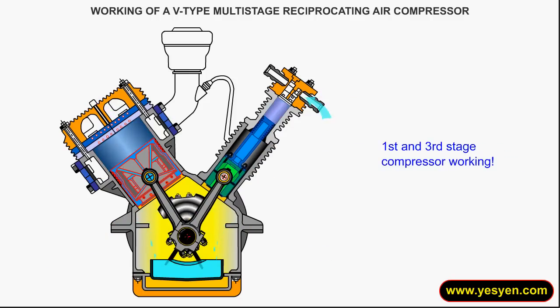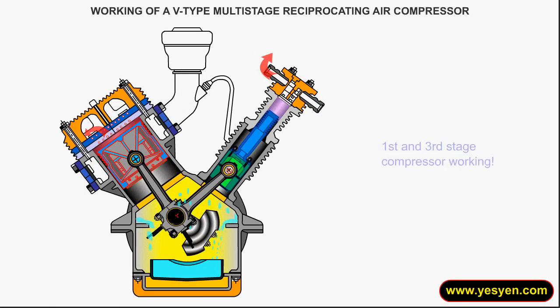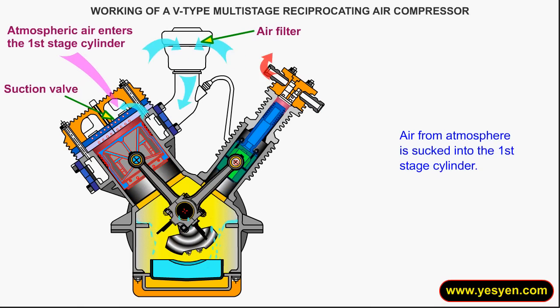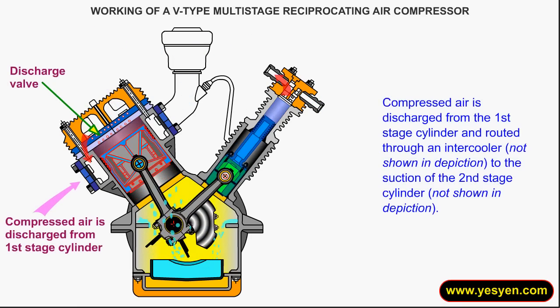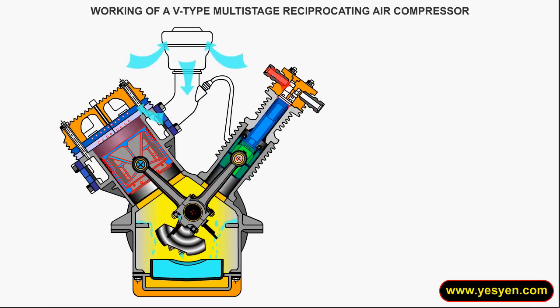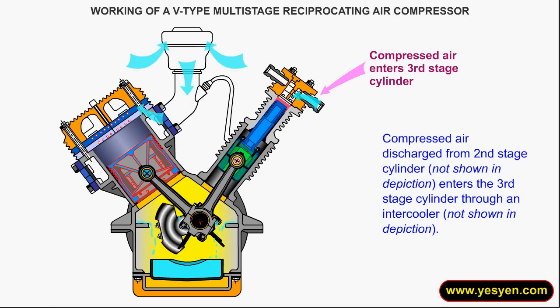First and third stage compressor working. Air from atmosphere is sucked into the first stage cylinder. Compressed air is discharged from the first stage cylinder and routed through an intercooler to the suction of the second stage cylinder. Compressed air discharged from the second stage cylinder enters the third stage cylinder through an intercooler.